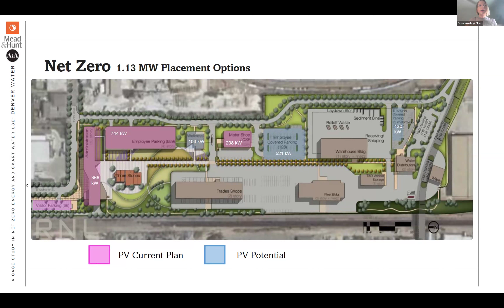Talking about the strategies here, there's a number of things at play. I've hinted at a few of them, and many will look familiar having gone through the previous presentations, but there's still a few interesting things to talk about. I did mention that the building was post-tension concrete with a radiant heating and cooling system included. There are two reasons for doing that. One, it brought down the overall height of the building - we could stay out of high-rise classification, which helped us on overall cost - but it also provided super efficient heating and cooling coming in the downward direction from the ceiling above. We then provide fresh air from the raised floor system below.